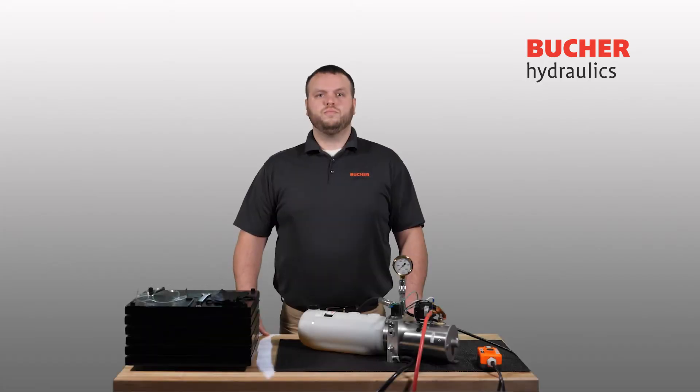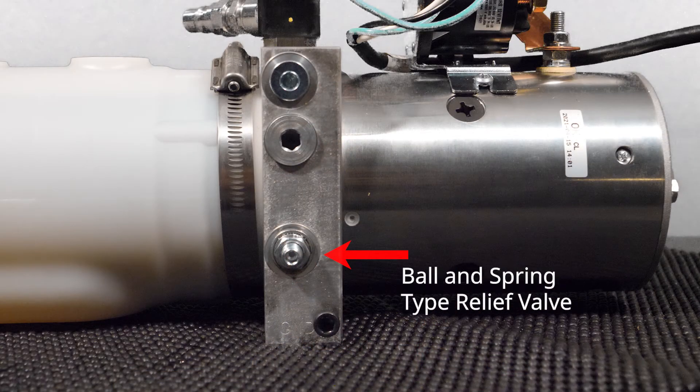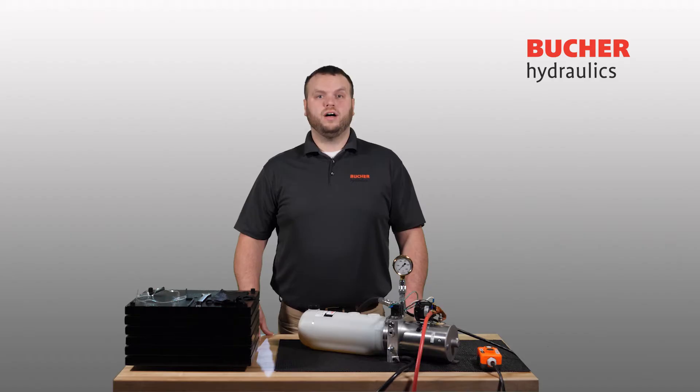There are two primary relief valve types used in Bucher Hydraulics Power Units: Ball and Spring Type and VM01 Conical Poppet Type. These valves are easy to identify from the exterior of your Bucher Hydraulics Power Pack. As you can see here, a ball and spring type relief valve has an exposed adjustment screw with a recessed 3/16th hex drive. The VM01 valve, on the other hand, typically includes a hexagonal cap that covers the adjustment screw, as you can see here.